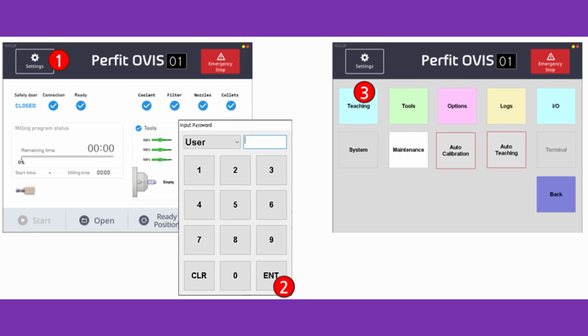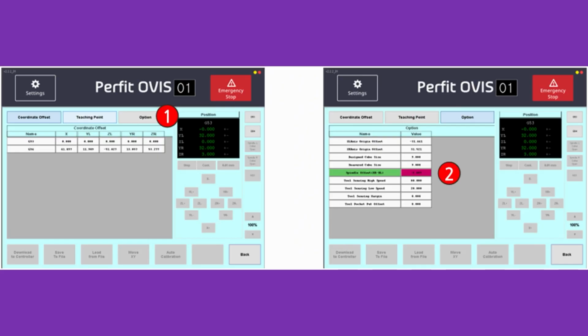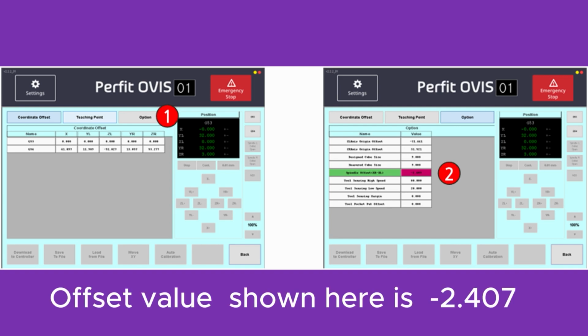We will begin by updating the spindle offset values in the Millbox software. These values change whenever an auto calibration is performed. Enter the settings menu, click enter to bypass the password, and select teaching. Click the option button on the top of the screen and then note the spindle offset value. In this case, it is negative 2.407.